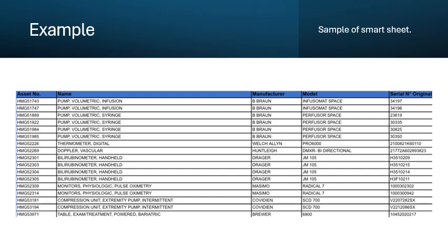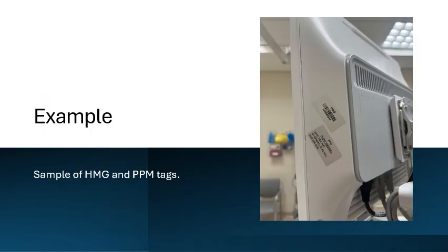For example, this is the Smartsheet we used. First you have the HMG number, the asset number, which includes the HMG number — HMG stands for Habib Medical Group. Then we have the name of the device, the manufacturer, the model, and the serial number, which differs from device to device. This helped us find the asset number and locate the device, then go to head nurses to confirm we could find it. Here you can see a monitor that has the HMG tag and the PPM. The PPM is for maintenance, so we know after how many months or years the device needs to be rechecked for calibration, electrical tests, safety tests, and so on.